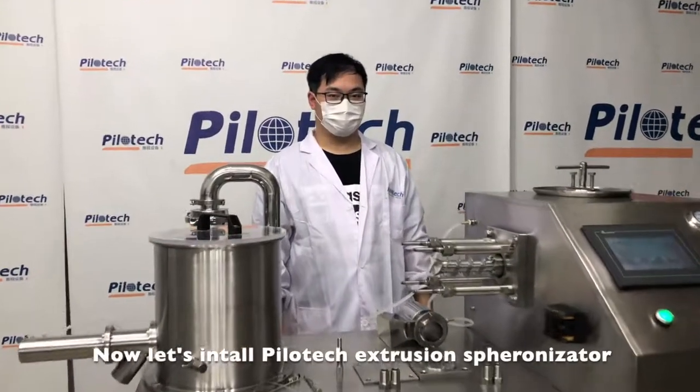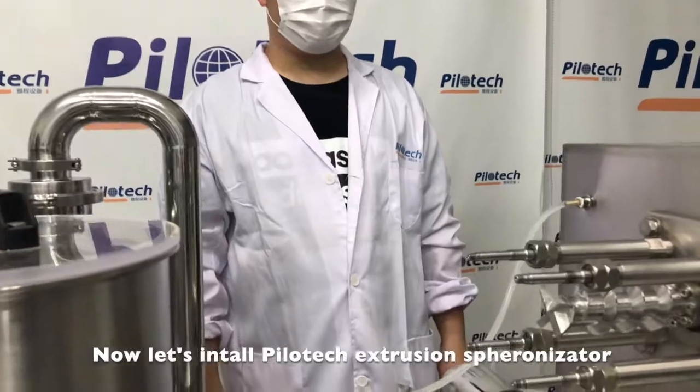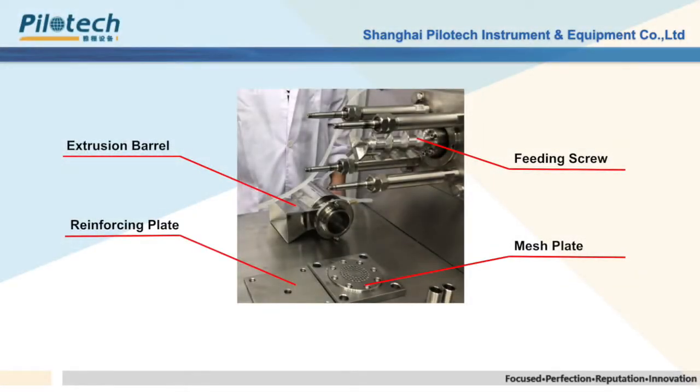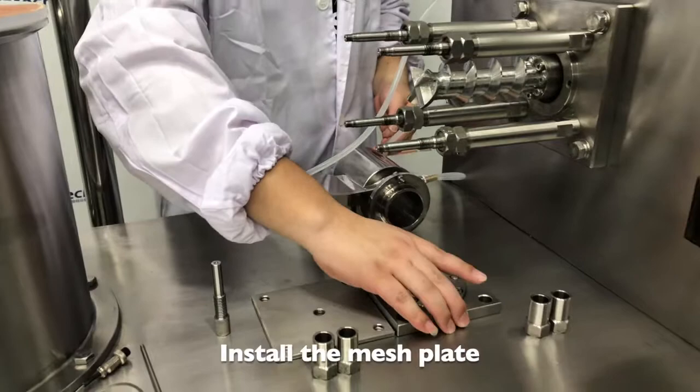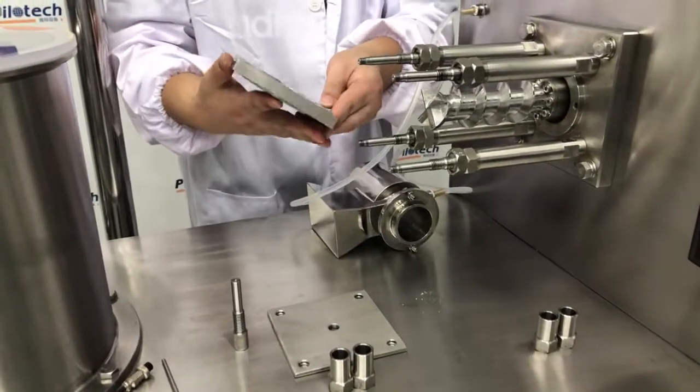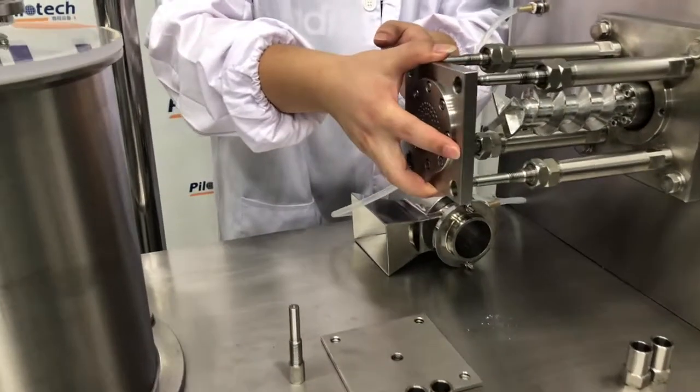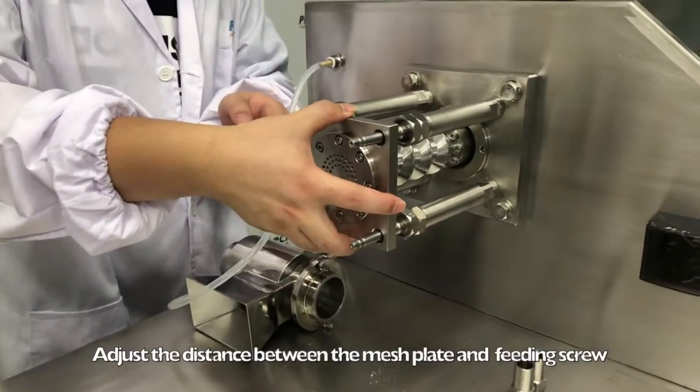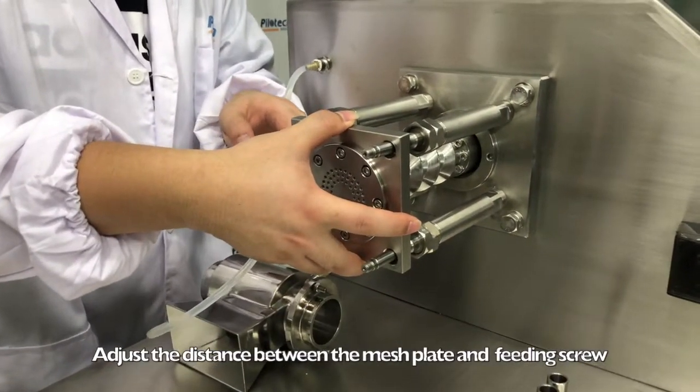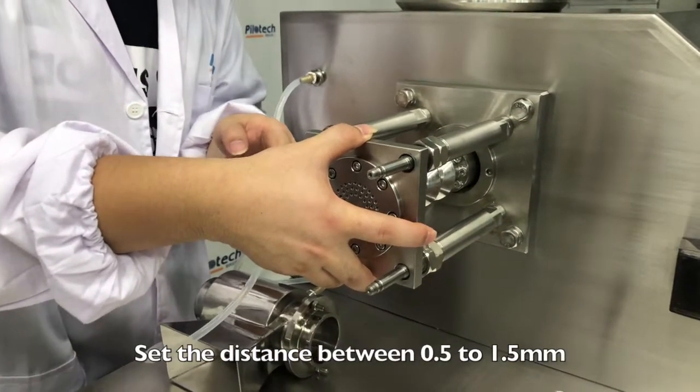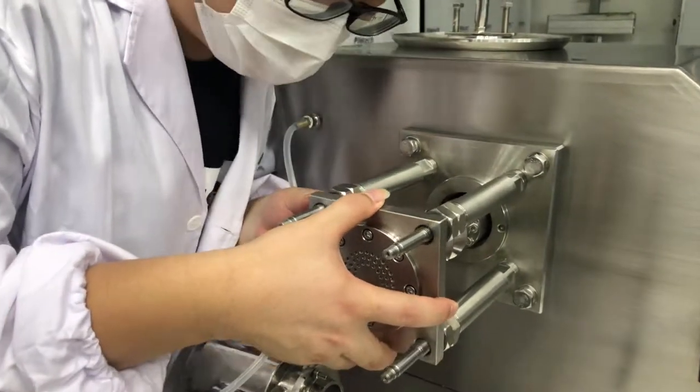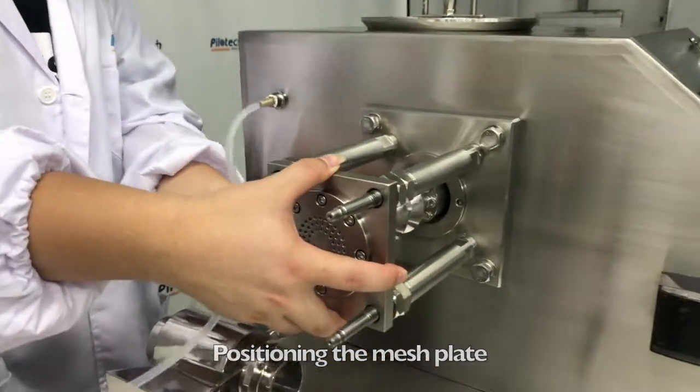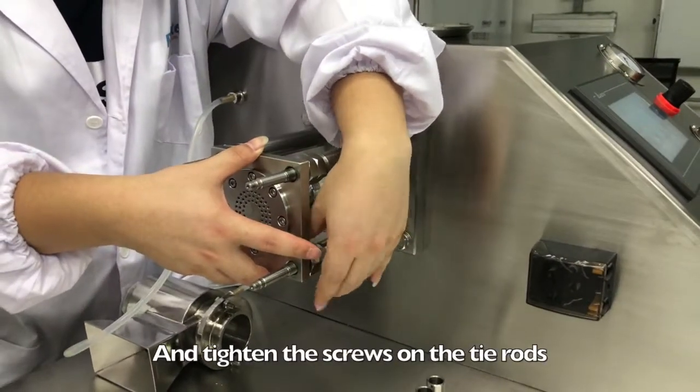Now let's install PILOTEC Extrusion Spheronization machine. Install the mesh plate. Adjust the distance between the mesh plate and the feeding screw. Set the distance between 0.5mm to 1.5mm. Position the mesh plate and tighten the screws on the tie rods.